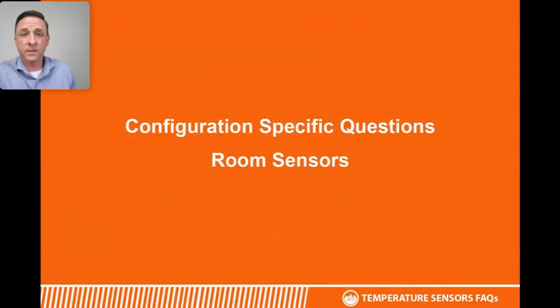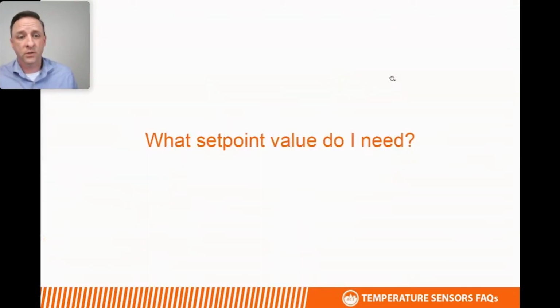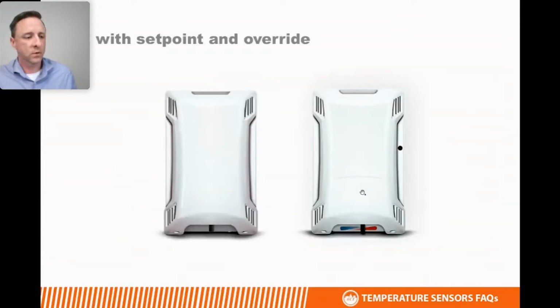Moving into some of the more specific configuration questions, starting with room sensors, a common question is, what set point value do I need? The set point is that slide potentiometer that you see on the bottom of the sensor, and it's a separate secondary output distinct from the temperature sensor. A lot of people don't realize that it's a second resistive output distinct from the temp sensor. So when we ask a customer what set point they need, they'll say 10K. Well, that might be the 10K thermistor. That's the temperature sensor, but the set point is a different output.